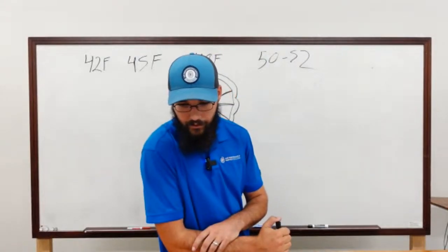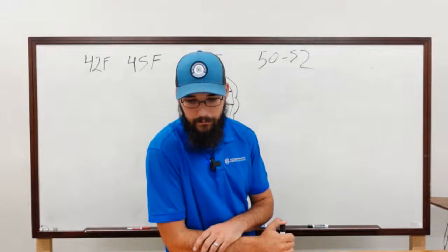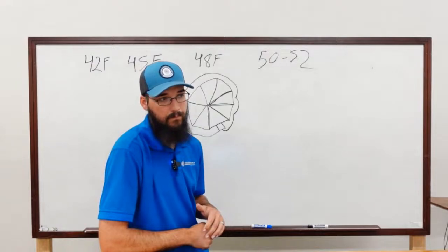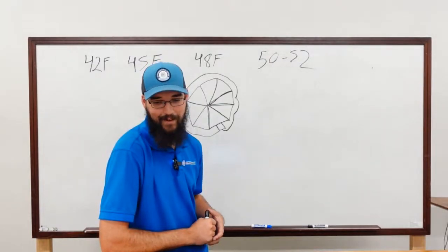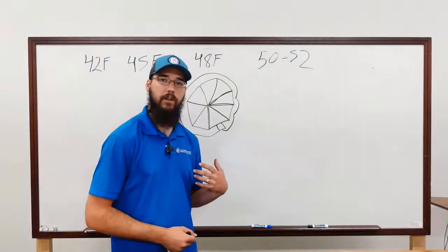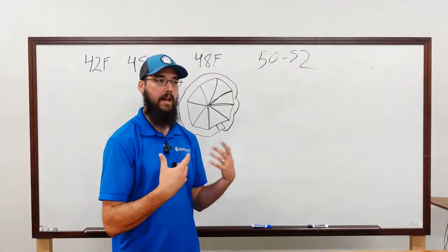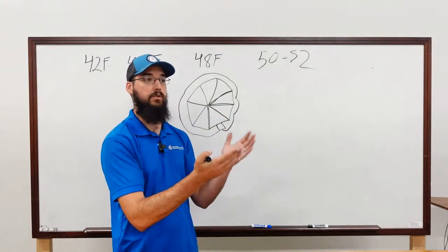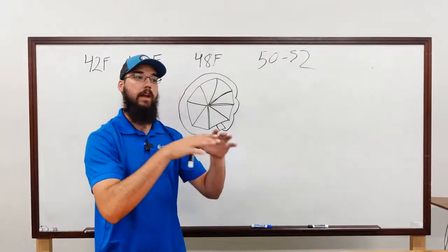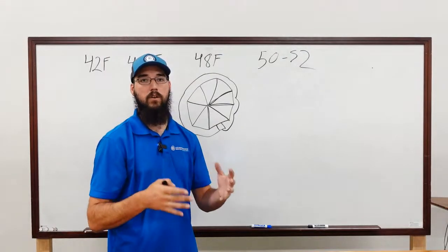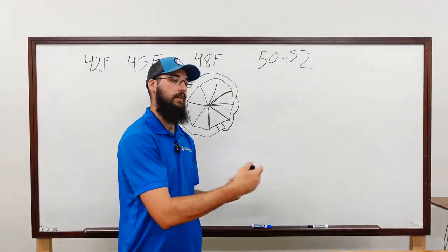The guide vanes closing decreases current draw, just like restricted airflow lowers amp draw on the blower. Exactly. Yep. That is right. Yes, it does. It keeps the amp draw lower because we don't have any input. Same reason why, when we unload the screw compressor and the slide valve moves, current draw is proportional to load. Load is proportional to how much refrigerant we're moving. So as we lower the load on the screw or the impeller, either way you look at it, we are reducing the current draw required to turn it, because that is effectively horsepower.